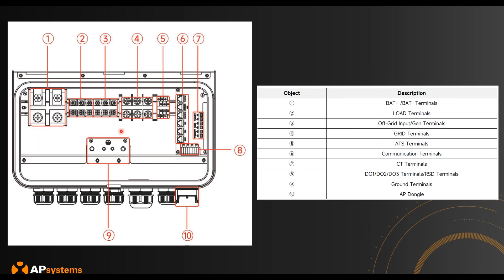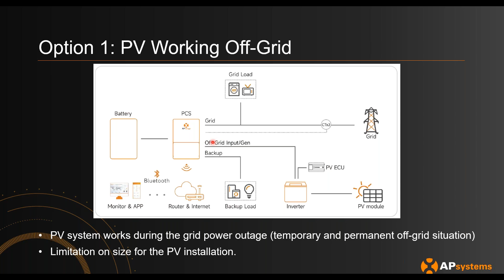There are basically two ways that you can connect solar to the system. The first way is to connect it directly into this port over here, the off-grid terminal. By doing so, you will have solar continue to produce power when you have a grid outage. But the main downside is that if the solar inverter is connected here, there is going to be a limitation on how much solar you can put in here.